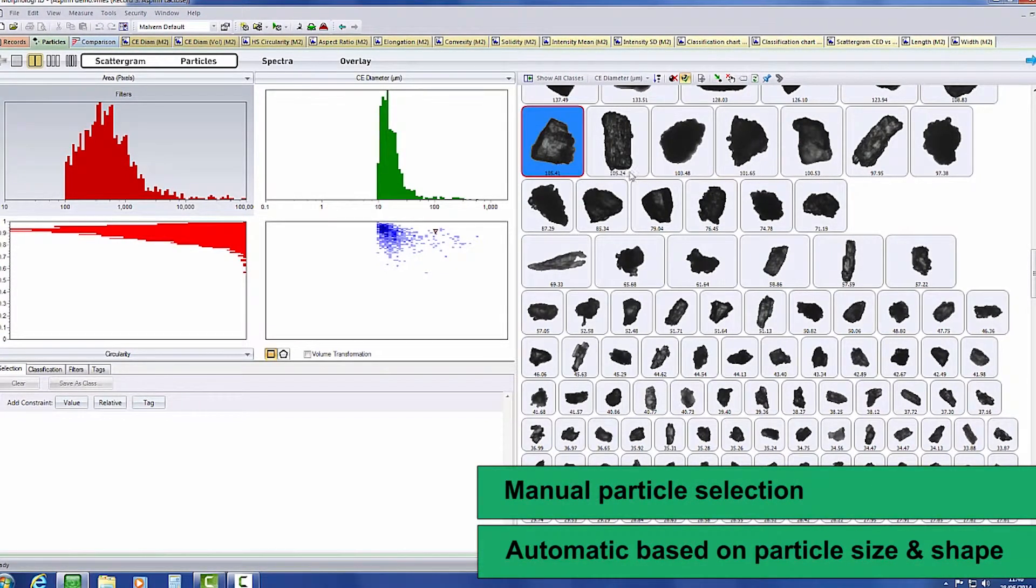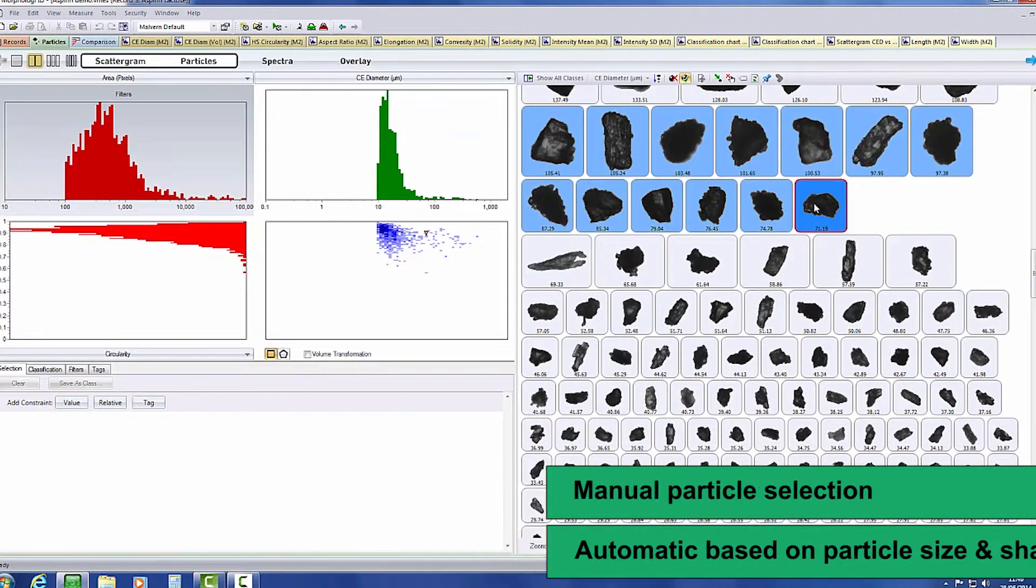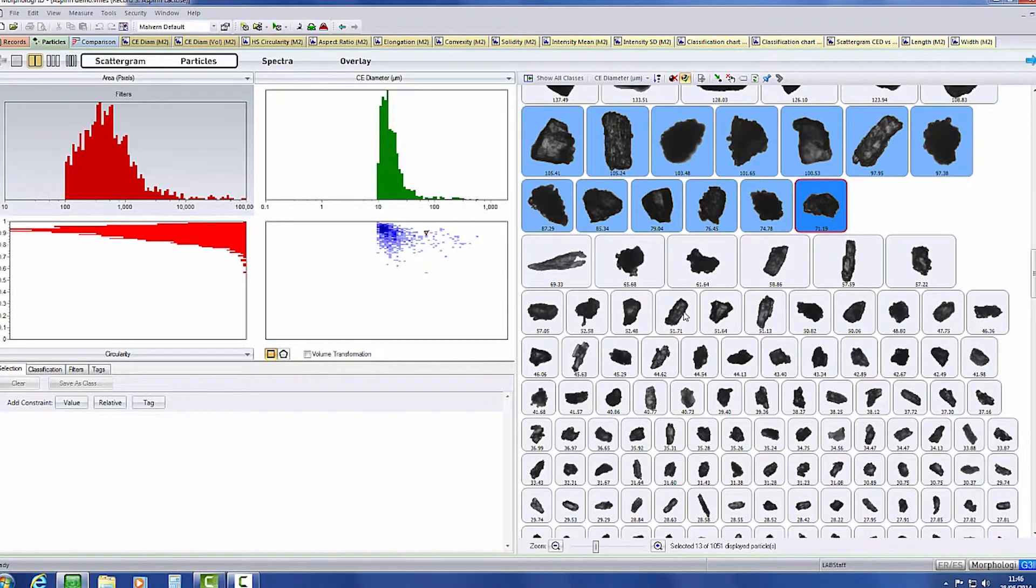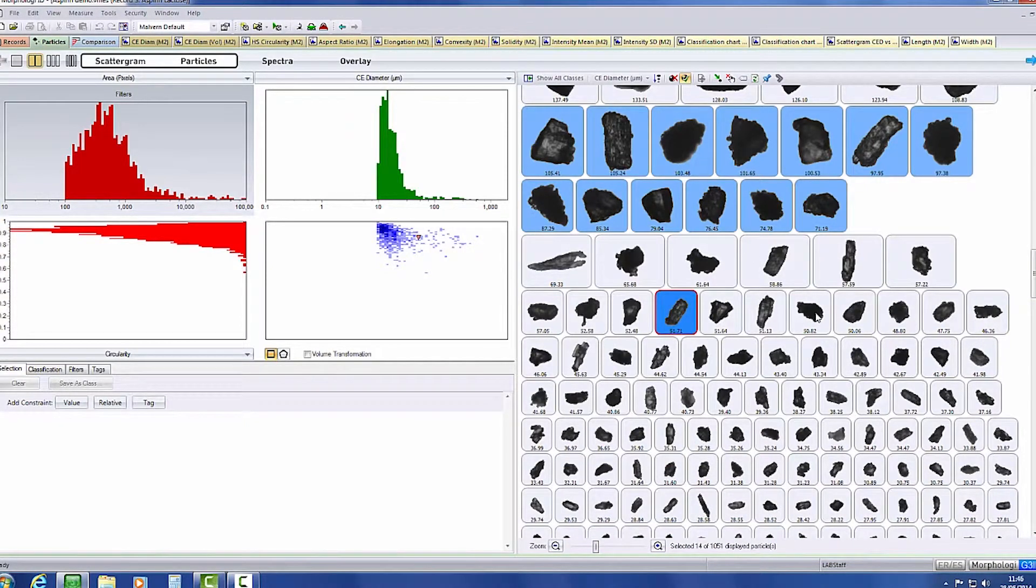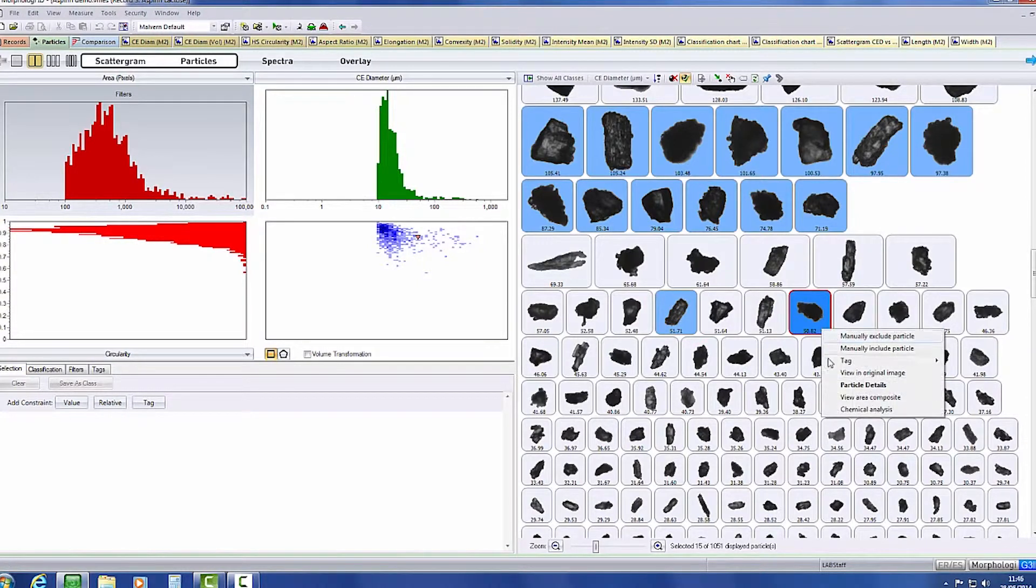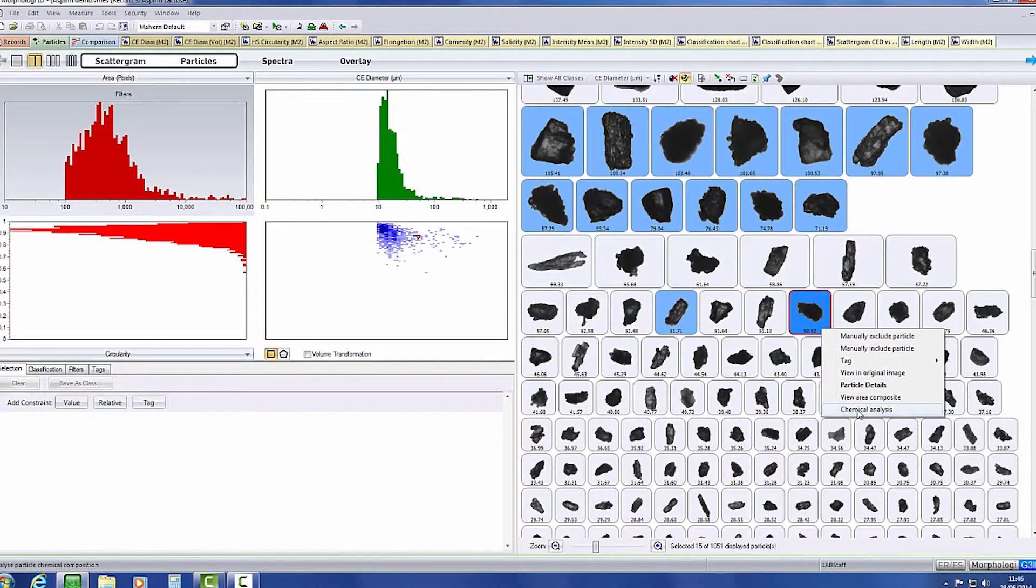Particles can then be targeted for Raman spectroscopic analysis. Targeting can be carried out based on manual selection of particles from the particle view, objective particle selection by the software, or automatic classification of particles of interest for identification based on specific size and shape parameters.